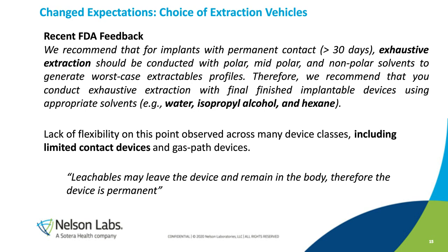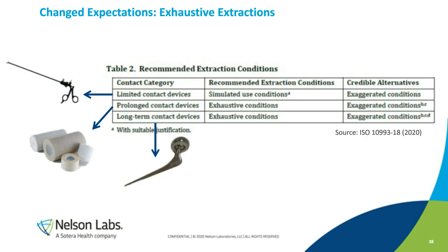And just understand that even if the scientific argument is good, really the policy and expectation is that you have 3. And part of this is built into the new ISO 10993-18. You can see here there are different recommended extraction conditions inside that document.